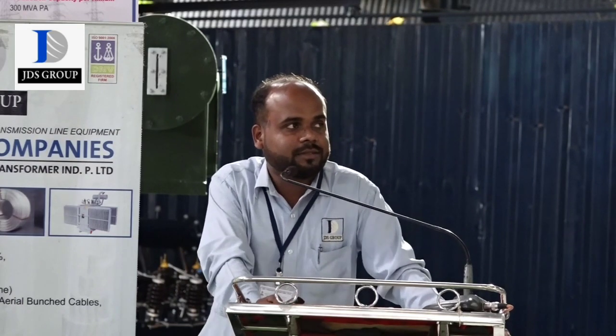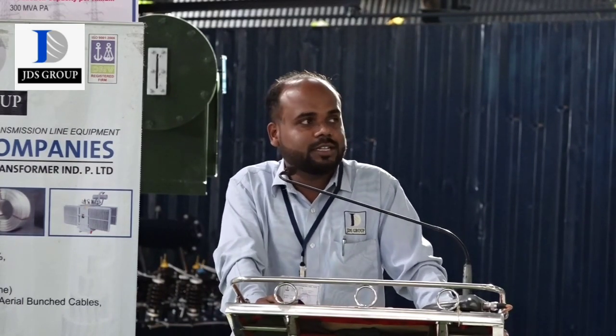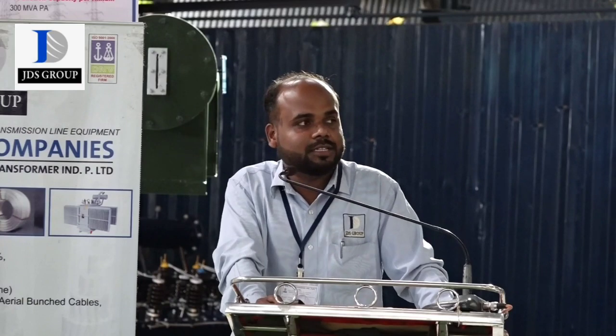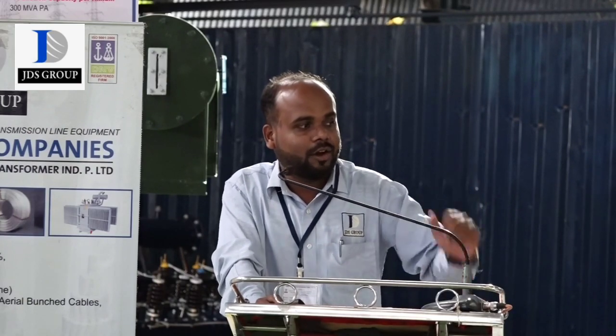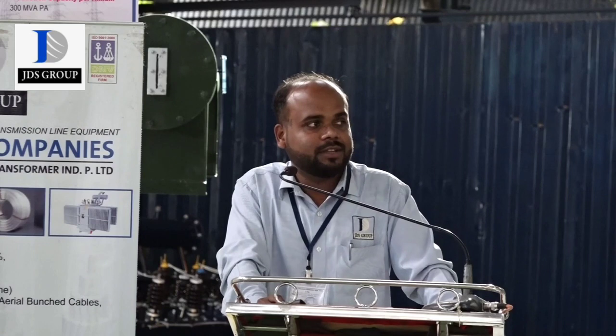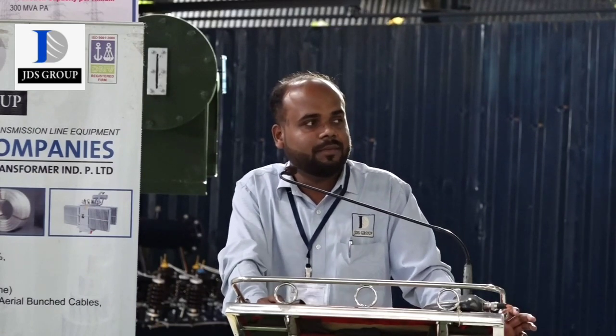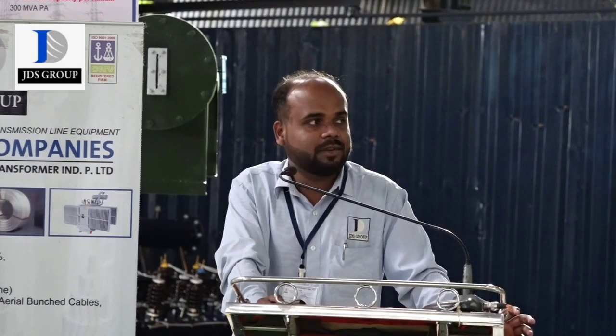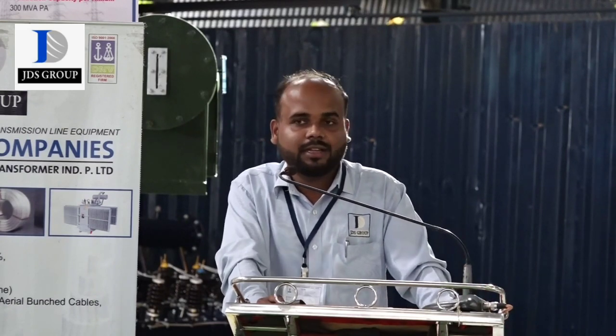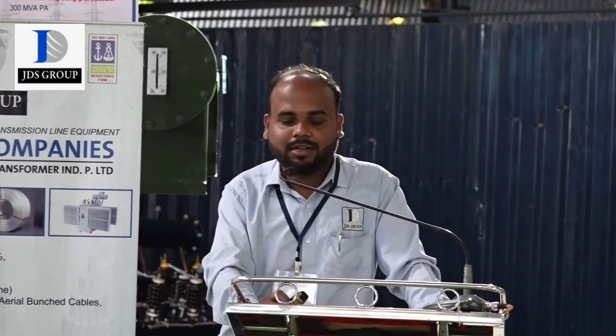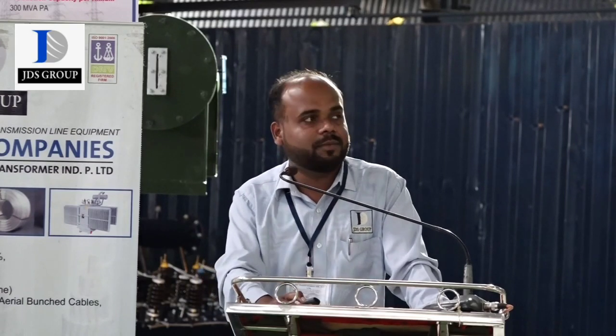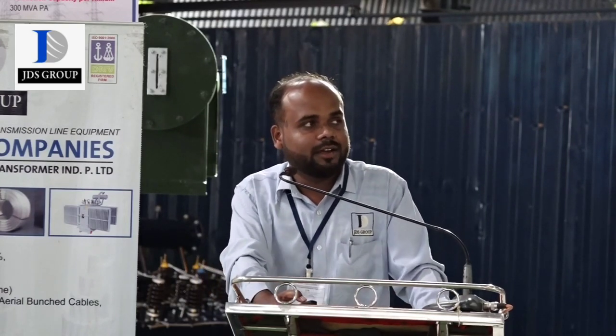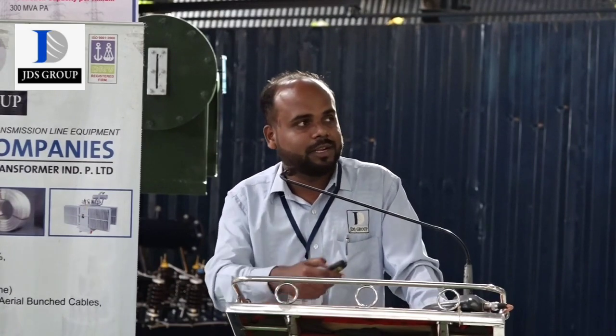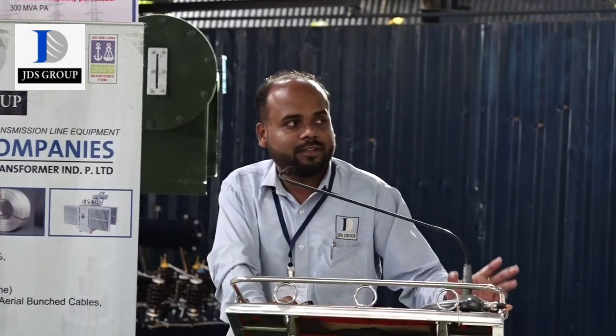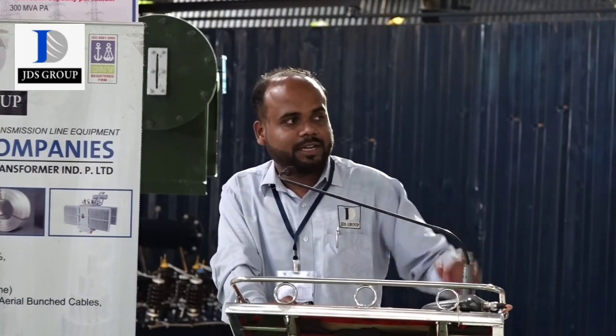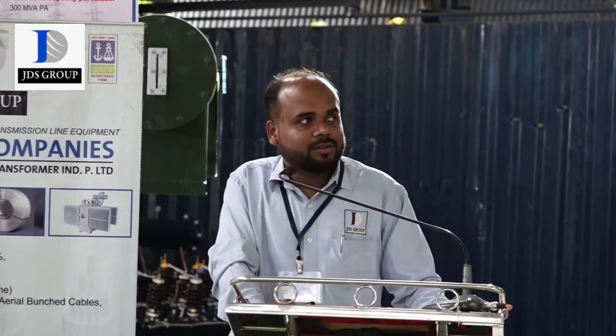Next, the transformer oil that we are using: is it of good quality or not, and how much is the breakdown voltage? We do an oil test. In the oil test, the minimum value we recommend for our transformer is 60 kV. That is good for using the transformer. In each and every transformer, before oil filling, we do the oil test. And after this the oil of the transformer has been checked and it is ready for dispatch.